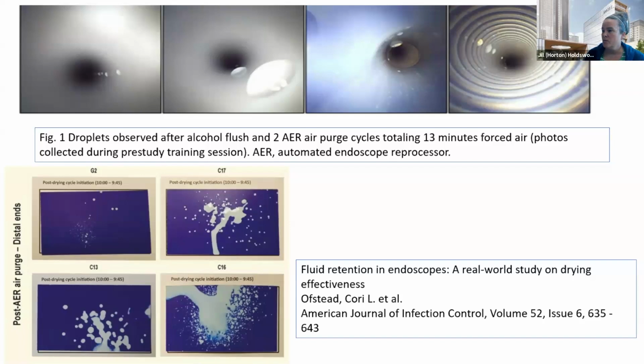You can see some of the photos we took with the borescope and the lumens of some of these scopes. And what you see on the blue cards down here is what we blew out with turbulent air onto these cards that caught water. So water and droplets inside these scopes, they can cause bacteria to grow if they sit in there while it's hanging in these cabinets. So this study shows how much water can really still be sitting in these scopes even after that approved 10-minute cycle in these AERs.